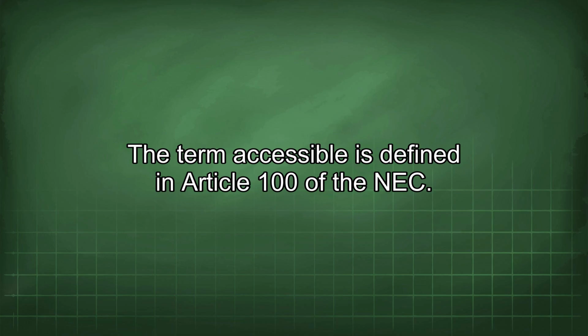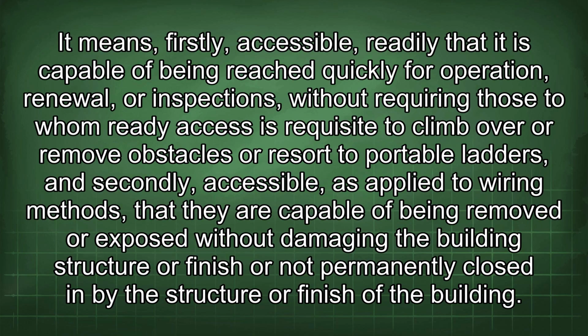The term accessible is defined in Article 100 of the NEC. It means, firstly, accessible, readily: capable of being reached quickly for operation, renewal, or inspections, without requiring those to whom ready access is requisite to climb over or remove obstacles or resort to portable ladders. And secondly, accessible, as applied to wiring methods: capable of being removed or exposed without damaging the building structure or finish, or not permanently closed in by the structure or finish of the building.